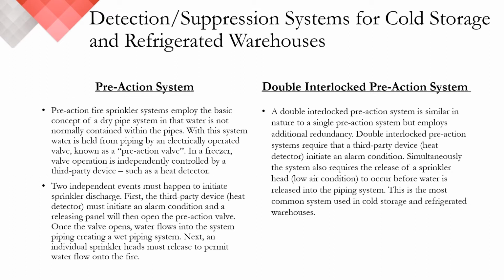fire or heat event. A double interlock pre-action system also uses a dry sprinkler system, but with an additional level of redundancy or protection. This system also requires an initiating device, such as Protectowire, to initiate an alarm condition. However, unlike a pre-action system, water is not released into the sprinkler piping by the activation of a single initiating device. This system also requires a sprinkler head to operate, thereby creating a low air condition within the sprinkler pipes. The combination of an initiating device alarm as well as a low air condition within the sprinkler piping then allow water to begin to flow.